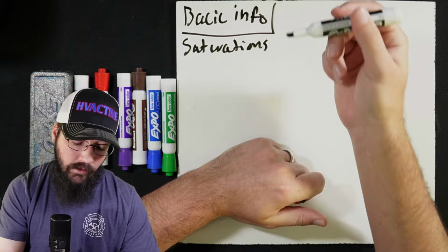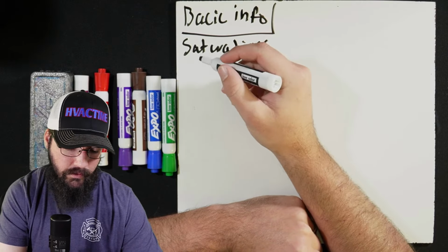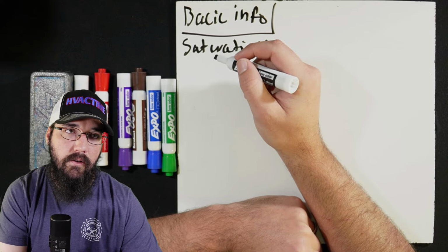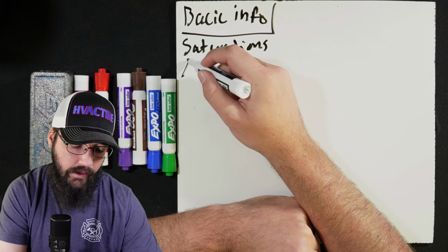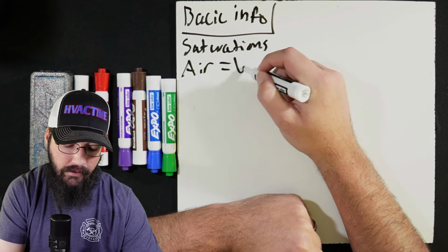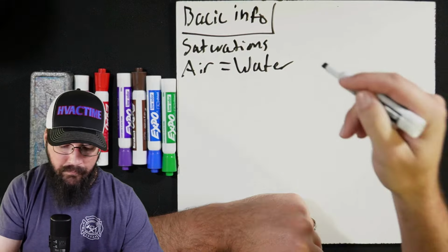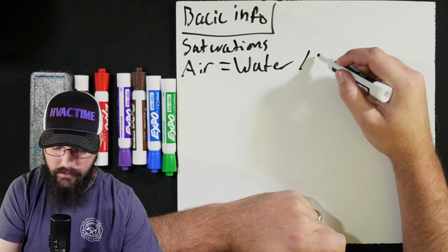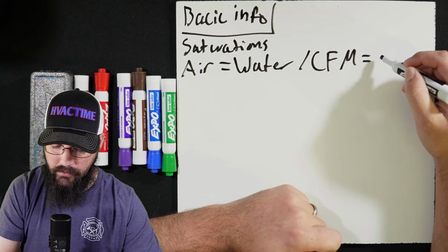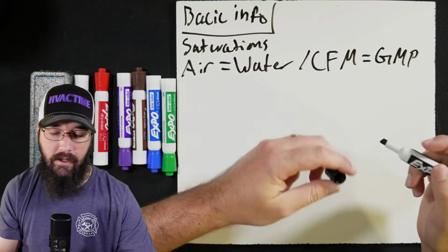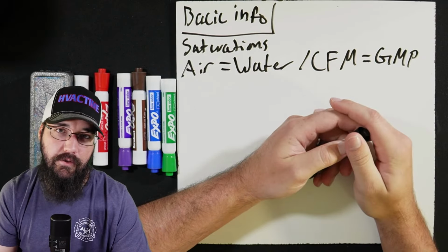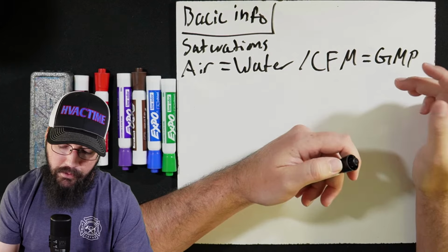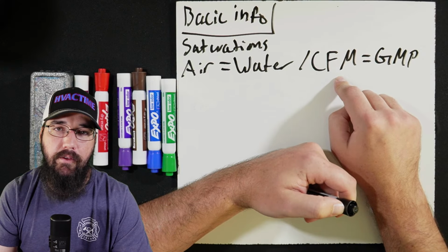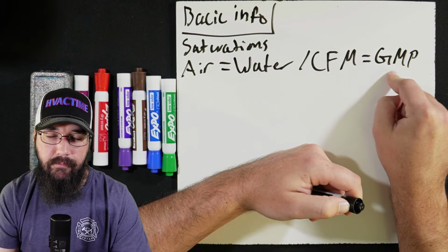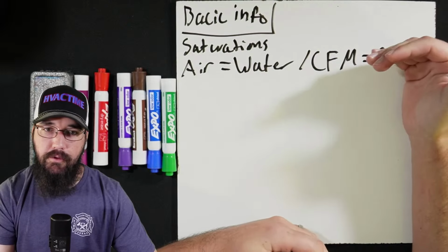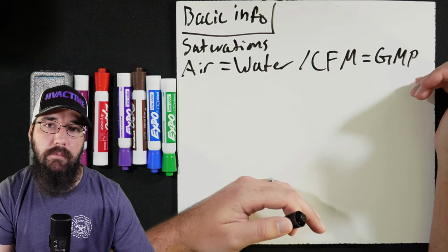Okay. Some other things to know is all the ways that you think about how we use air, think about it in terms of water. Okay? So what this could mean would be our CFM is equal to GPM. Not in a literal like for like, it's not 2000 CFM for every 2000 GPM. It's not a one for one. But the same symptoms you have with low airflow, you have with low water flow. Okay? A lot of our troubleshooting doesn't change the symptoms we expect to see.